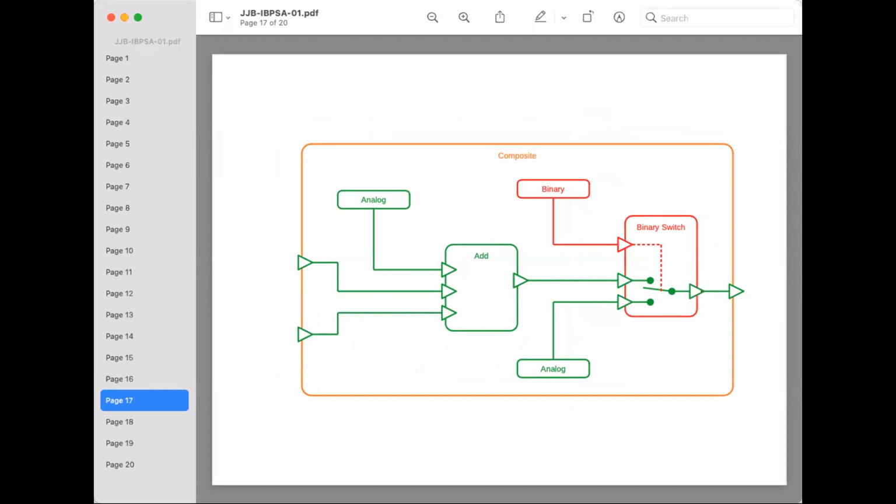So in addition to BACnet, which is ASHRAE 135, there's an additional effort to design a controls description language in ASHRAE 231, which is a combination of graphical and text-based programming derived from Modelica. So there's over 100 of these elementary blocks that can combine into composite blocks and be extended with proprietary blocks.